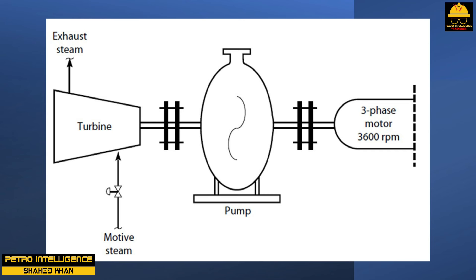But suppose the amp load on the motor drops to zero by gradually increasing the steam to the turbine, and then we increase the motive steam by another notch. Will the pump, motor, and turbine — all coupled together and hence running at the same speed — now run faster? The answer is no. What happens to the increment of shaft work generated by the turbine? This extra shaft work will be converted to electrical power — the three-phase motor will turn into an electrical power generator and begin to export electricity into the grid.